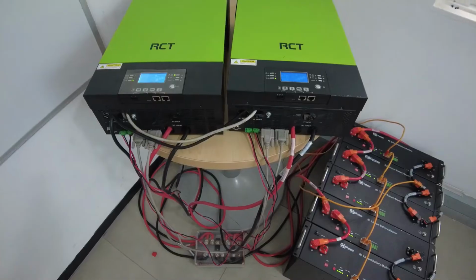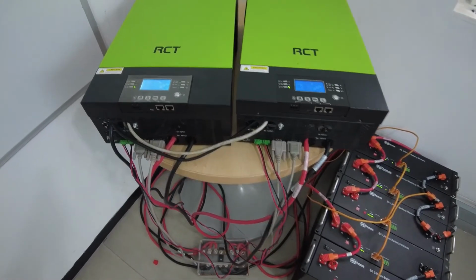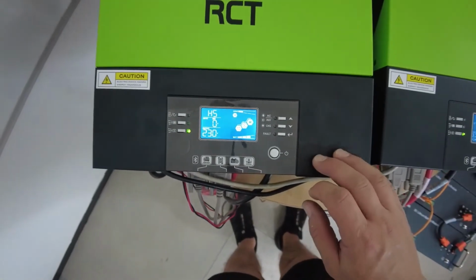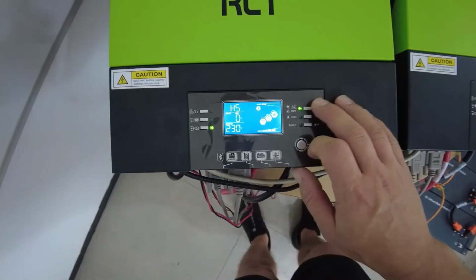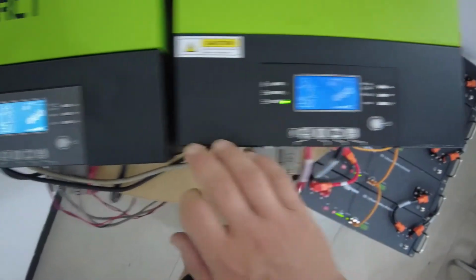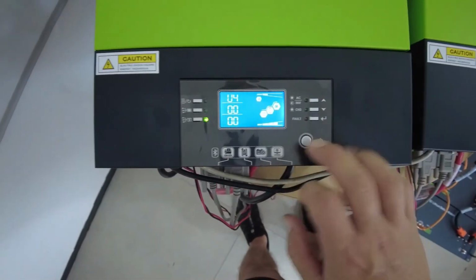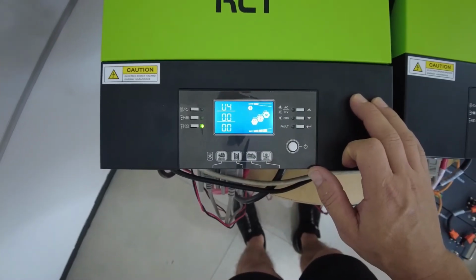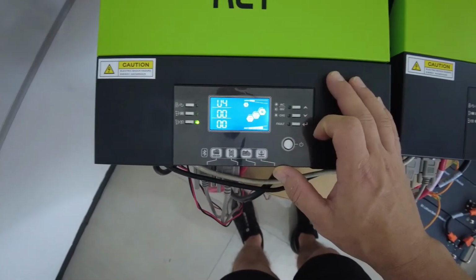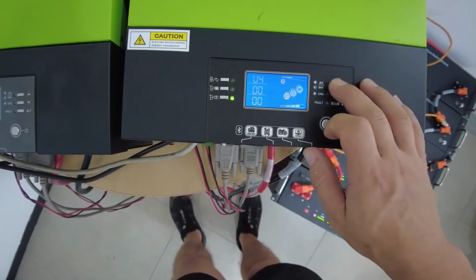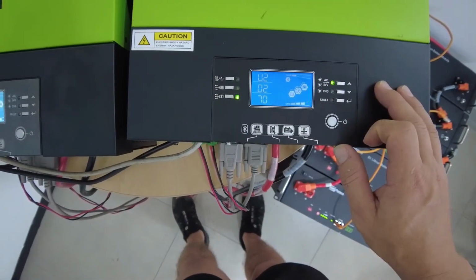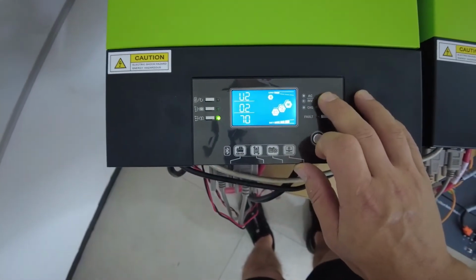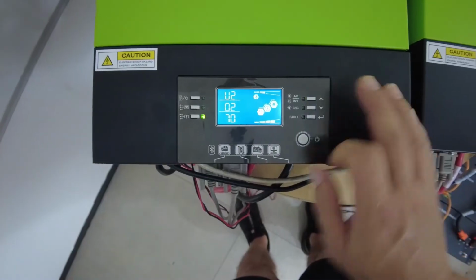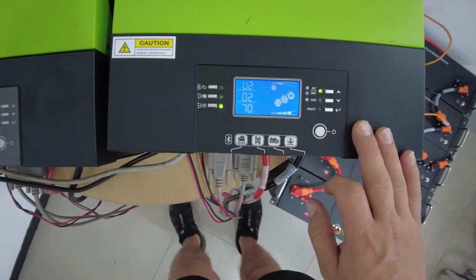Okay, now that the inverters have been connected and on, first thing I'd like for you to check is the firmware of the inverter. While it's on the home screen displaying this, just press the up button and it will start displaying a U1 number, sorry, U4. Press up, U4. I need you to check U2 0270, U2 0270. This is your remote panel firmware and it's the same.